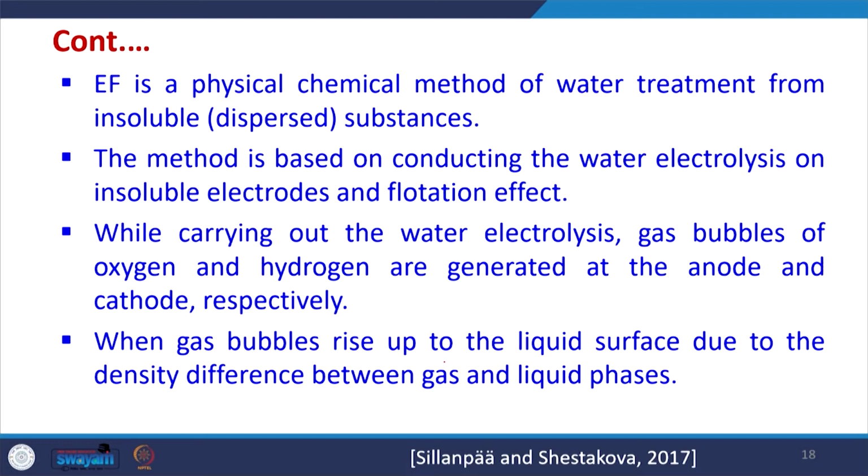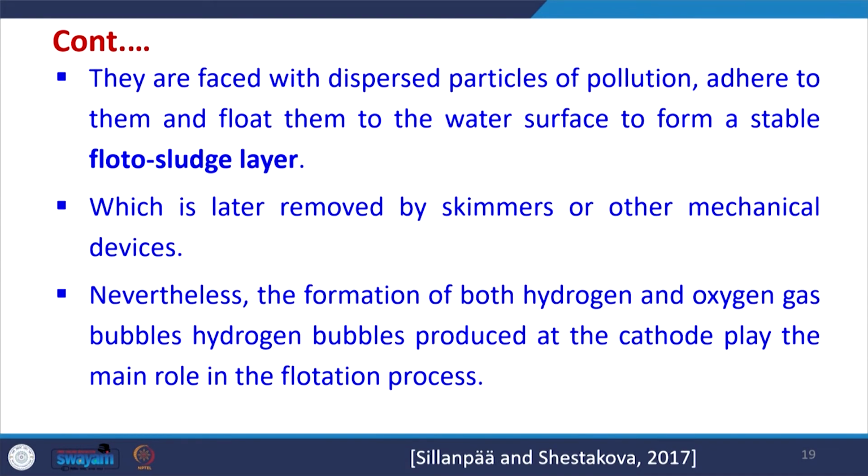When gas bubbles rise up to the liquid surface due to the density difference between the gas and liquid, they entrap a lot of organic compounds and meet the dispersed particles of pollutants. The pollutants adhere to them and are floated to the water surface to form a stable floto-sludge layer, which is later skimmed by various means, maybe mechanical devices, to remove them from the top of the surface.